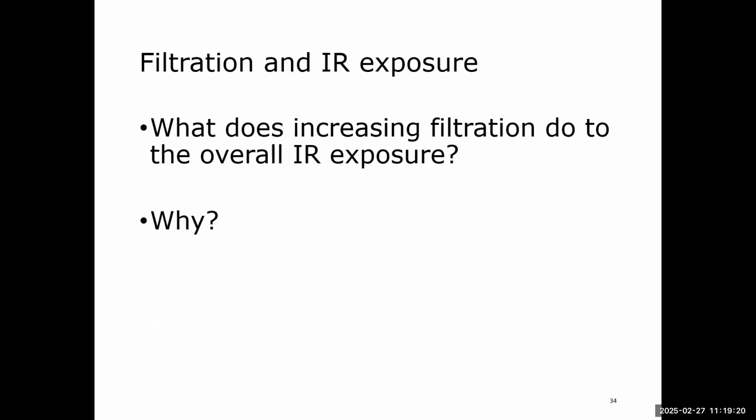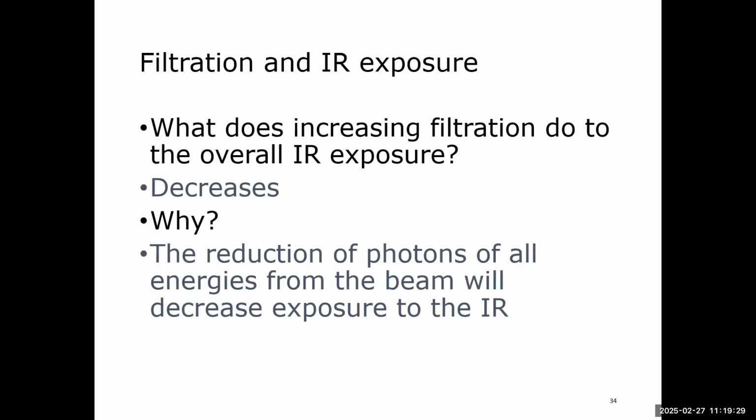Filtration and IR exposure. So what does increasing filtration do to the overall IR exposure? It decreases it. And the why is because initially when you're adding filtration, you're just going to filter out those very low energy photons that aren't going to do anything for you. They're going to do what, basically? Be what? In the skin dose, right? They're just going to get absorbed in the patient's skin, increase the patient's dose, do nothing for us as far as our image goes, okay?